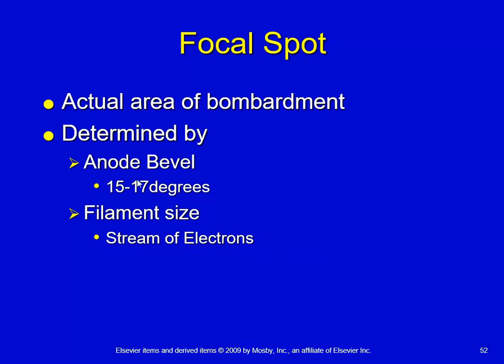We also have an anode bevel, which generally runs from 15 to 17 degrees — so it's very vertical. The bevel itself is at an angulation on the face of the anode. Generally, the smaller the number, the more steep it is, and the smaller your focal spot is going to be.